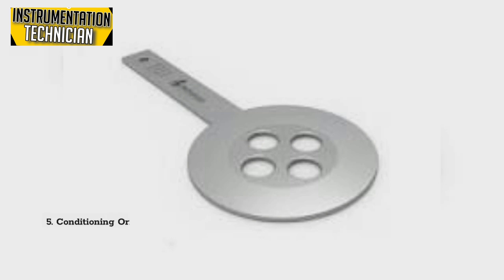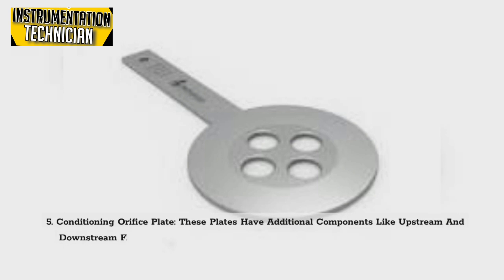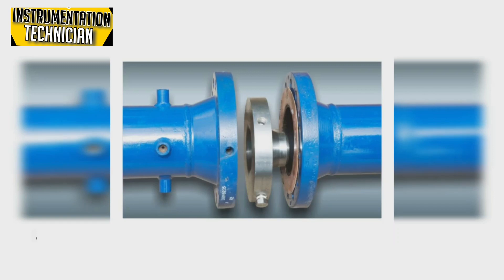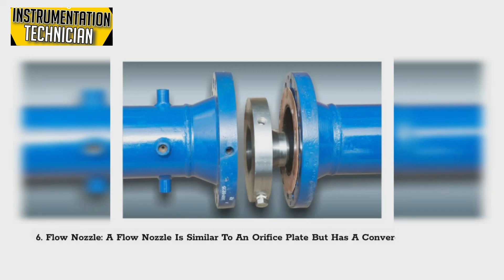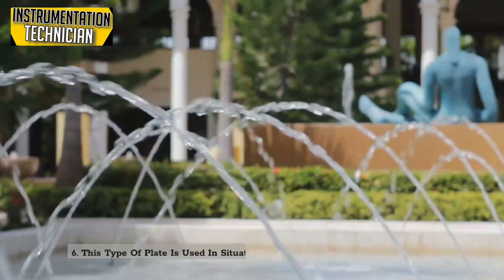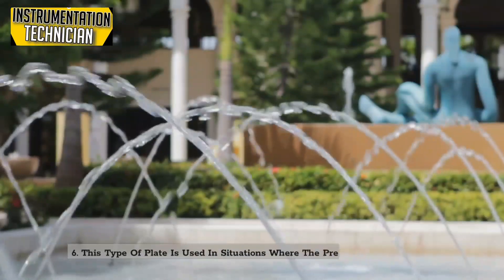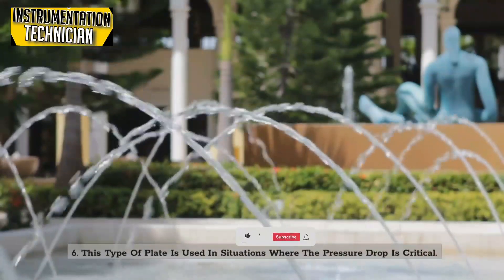5. Conditioning orifice plate — these plates have additional components like upstream and downstream flow conditioners, which are used to reduce turbulence and increase measurement accuracy. 6. Flow nozzle — a flow nozzle is similar to an orifice plate but has a converging inlet section and a diverging outlet section. This type is used in situations where the pressure drop is critical.